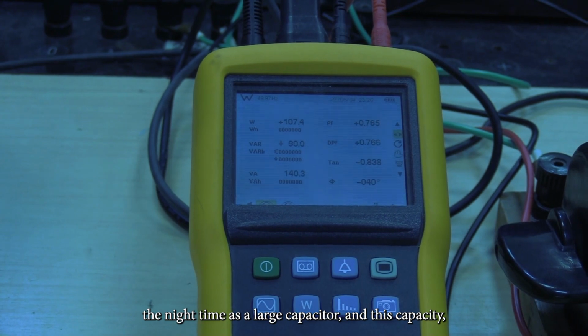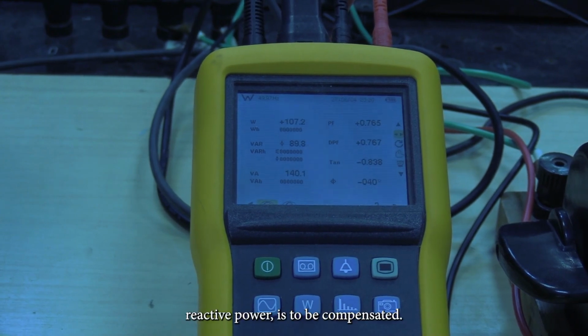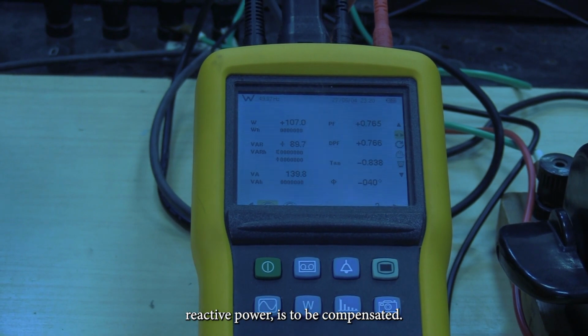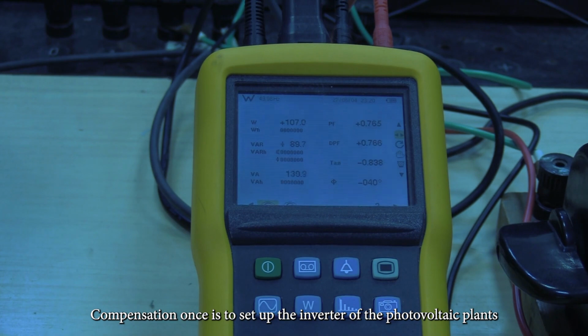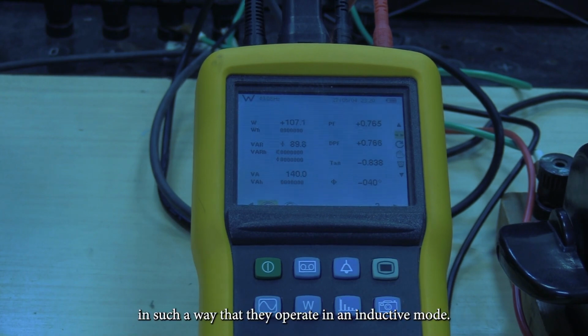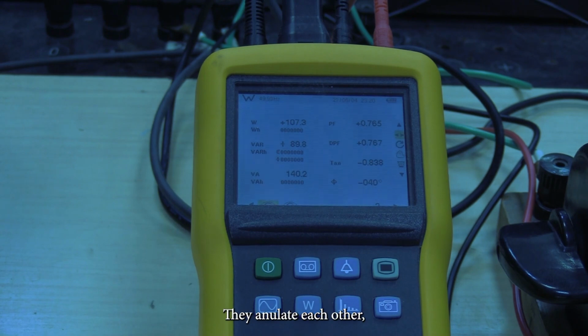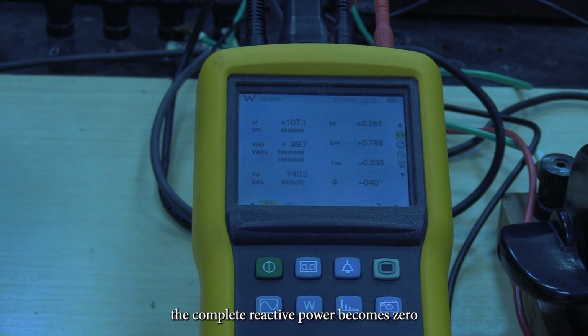And this capacitive reactive power is to be compensated. There are two kinds of capacitive compensation. One is to set up the inverter of the photovoltaic plants in such a way that they operate in an inductive mode, so antagonist mode to the capacitor. In this manner, they annul each other. Practically, the complete reactive power becomes zero.